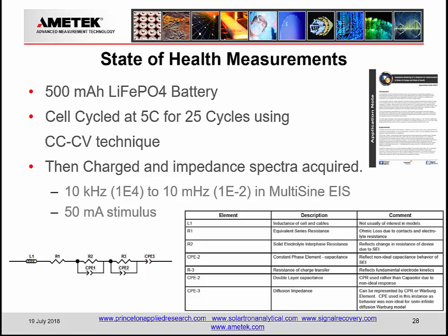So let's take a very similar experiment to what we just did for state of charge, but look at it as state of health. State of health basically studies the degradation in a battery. My comparison here is that you plug up your laptop on day one, and it tells you you have 4 hours of battery life left. Not a problem, you get all 4 hours. After 1 year of usage, when you unplug it and it tells you you have 4 hours of battery life left, after 30 minutes it's warning you you're running out of battery. So is the computer consuming more power? No, your battery has faded, and it's not as strong as it was from day one.